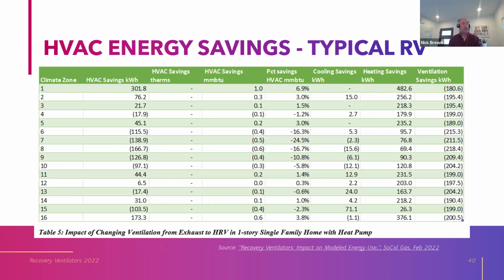Now there's a whole study. I'm going to send you guys this slide deck with the links so you can click on it and get more information as much as you want. But here is the impact of changing from exhaust to an HRV in a typical one-story single-family home with a heat pump with a typical recovery ventilator. Okay, notice in the far right, that's the extra ventilation energy that house is using compared to exhaust. That's the negative we start out with. But there's heating energy savings, cooling energy savings, depending on the climate zone. And so the HVAC savings is the sum of all those columns. That's the number we really care about.